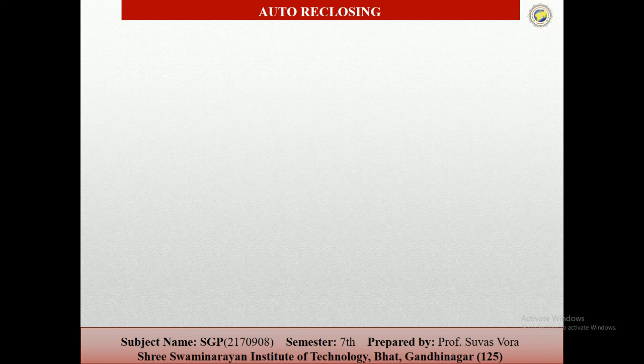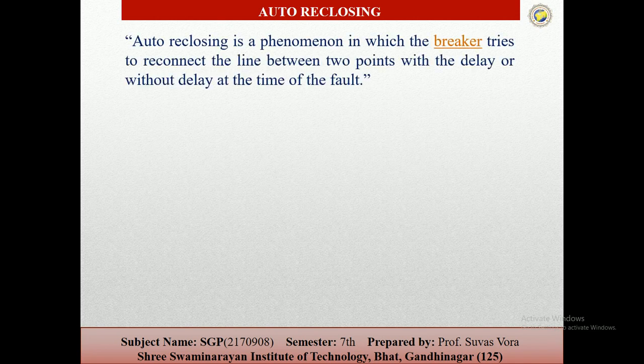Auto-reclosing: the main objective of an electrical power system is to maintain the continuity of power supply to consumers. In the event of a fault, the power supply is interrupted. About 80 to 90 percent of faults on overhead lines are transient in nature. Auto-reclosing is the phenomenon in which the breaker tries to reconnect the line between two points, with or without delay, at the time of a fault. If the supply is interrupted by the circuit breaker for a short period and the arc path is allowed to de-ionize, the line is re-energized by reclosing of the circuit breaker.